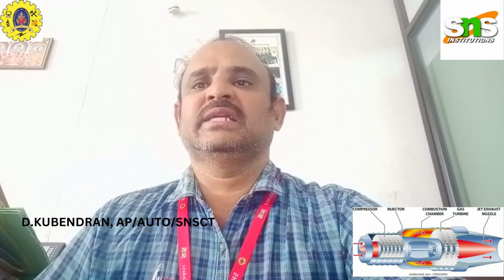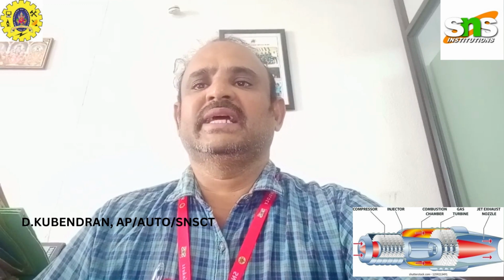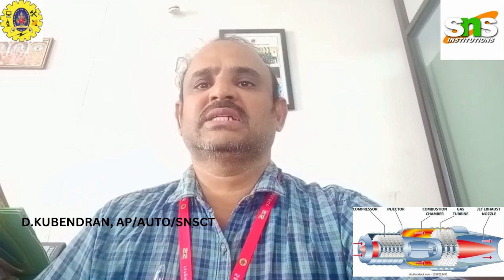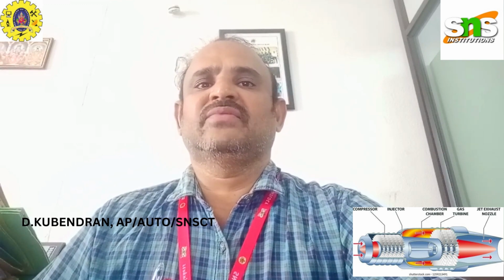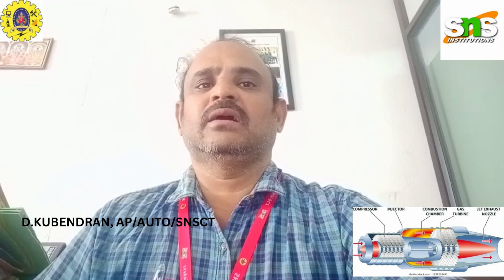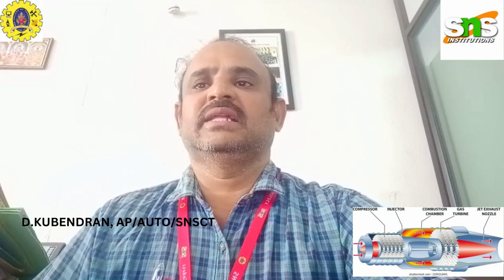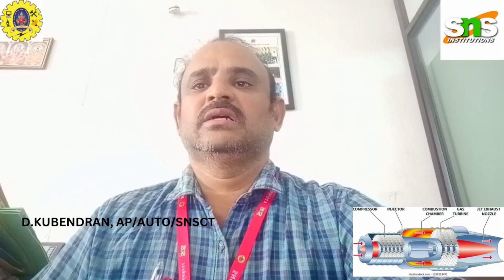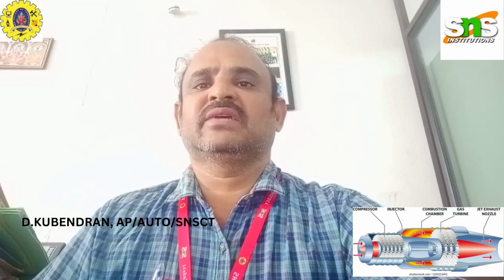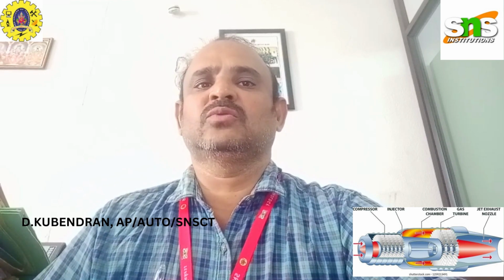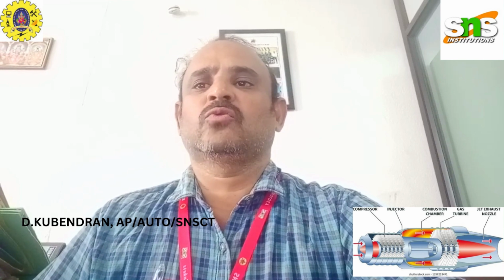Air is taken in by a compressor called a gas generator, with either an axial or centrifugal design, or a combination of the two. The air is then ducted into the combustor section, which can be of an annular, can, or can-annular design. In the combustor section, roughly 70% of the air from the compressor is ducted around the combustor itself for cooling purposes.